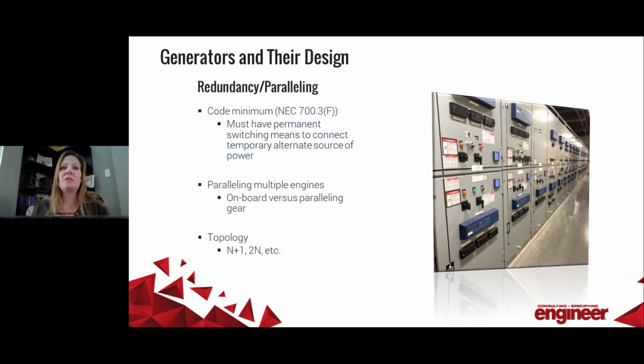So let's switch gears just a little bit and talk about how to apply generators in a system design and any redundancies that you may want to consider. So first off, we'll hit a little bit more codes again, but any emergency power system that is required to comply with the National Electrical Code Article 700, as James discussed earlier, is also required to have a permanent means to temporarily connect an alternate source of power.